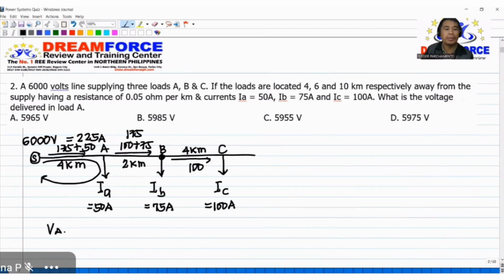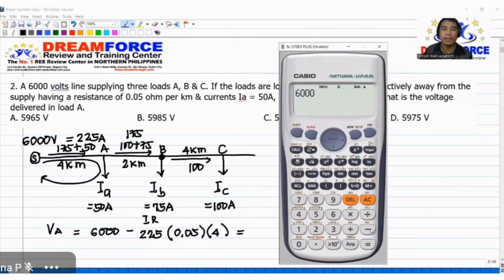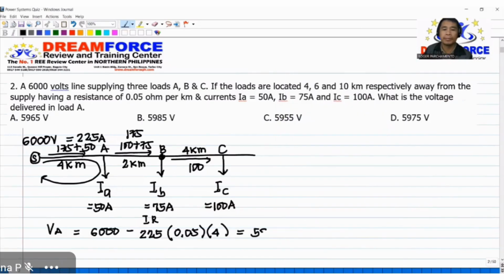If we make a loop here, VA is equivalent to 6,000 minus the drop here. Okay? The drop is current times the resistance. So the current at the source to A is 225 multiplied by the total resistance 0.05 ohm per kilometer multiplied by 4 kilometers. Solving, we have 6,000 minus 225 times 0.05 times 4 is equivalent to 5955. The letter C.